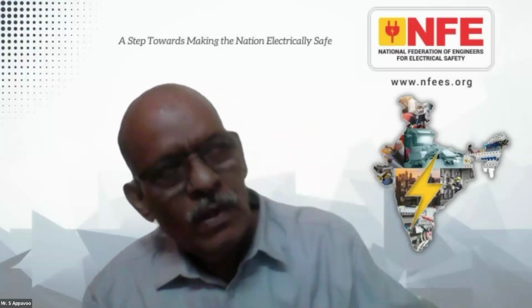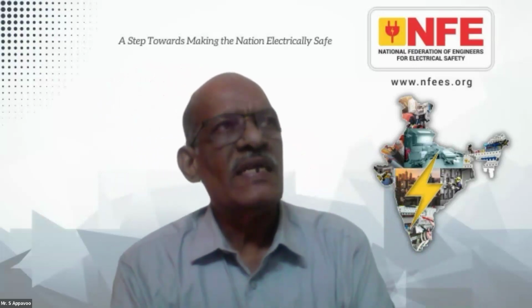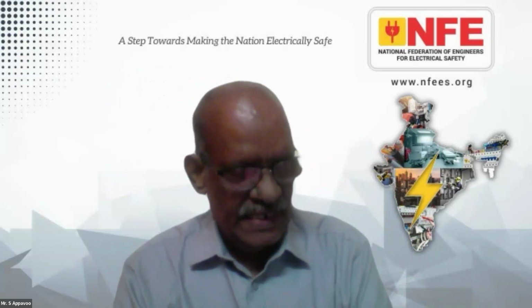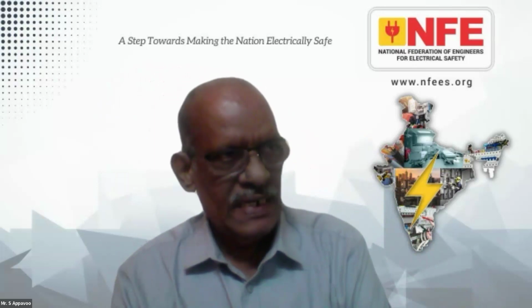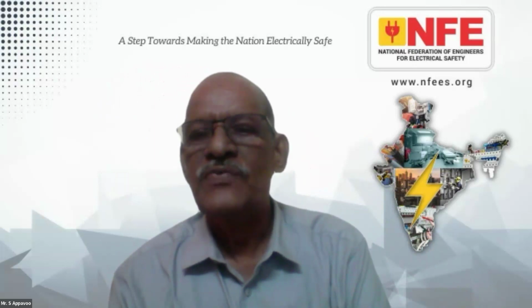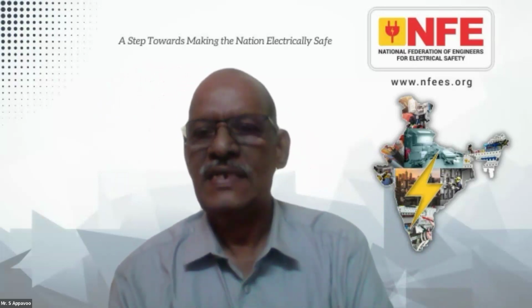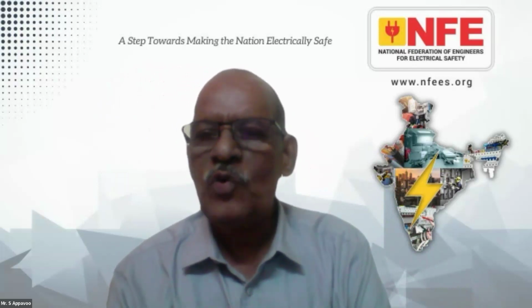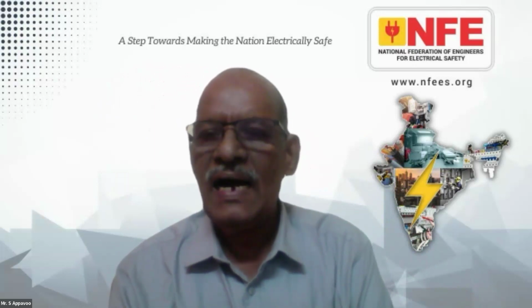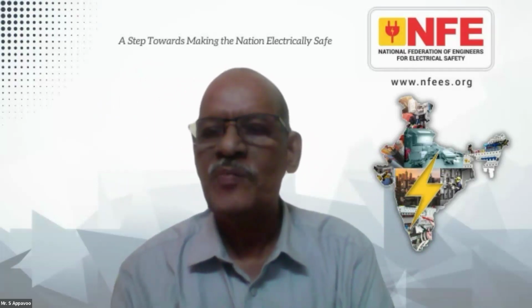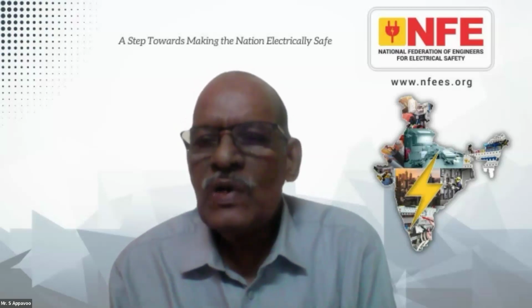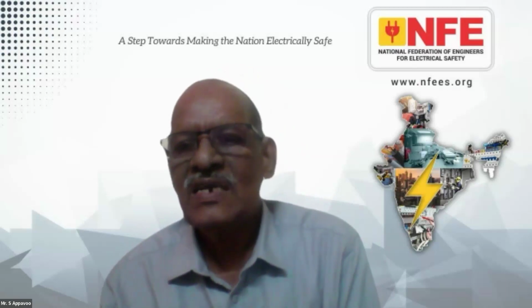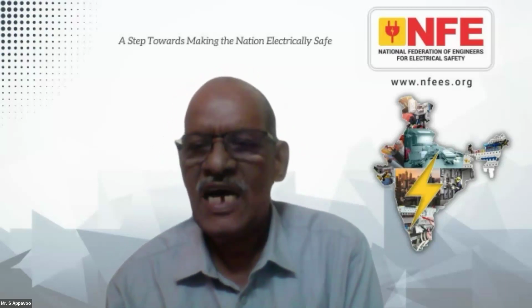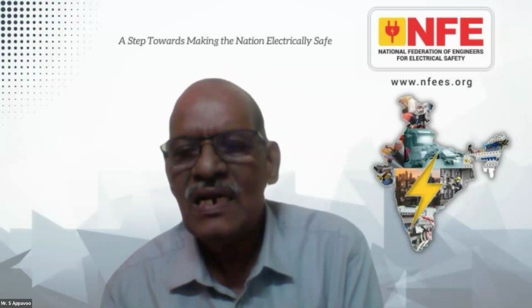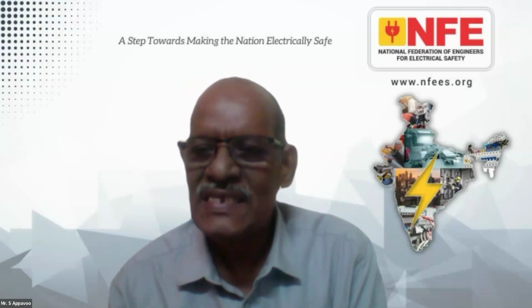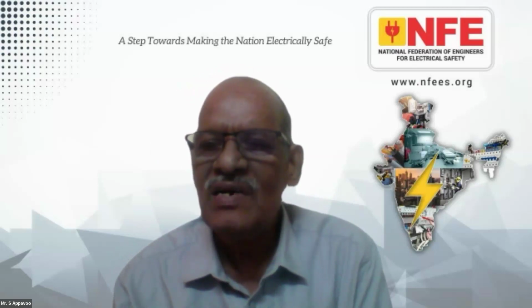I would like to supplement that view. That is the meter. The metering protocol is so stringent. With IEC 61000-4-30, Edition 3 meters have to be used for measuring the harmonic voltage. But the acceptable harmonic voltage is the burden of the grid as per IEEE 519. As per CEA regulation, they have strengthened the implementation by notifying it. The voltage harmonics are a result of current harmonics. That is another way. But you should be concerned with the current harmonics level as per standards. As per standards, it is not the individual current harmonic, nor the total current harmonics alone that is taken into account. It's the total demand distortion.